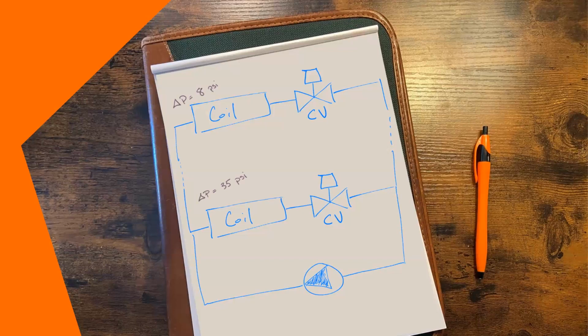The far zone typically has low pressure drops and therefore it's very controllable. The fact that there's no balancing valve won't have much effect on this coil or this zone. So with no balancing valve, that close zone is massively overpressurized and overflow is inevitable. The close zone is highly unstable and essentially behaves like an on-off control valve. We have bad valve authority there.